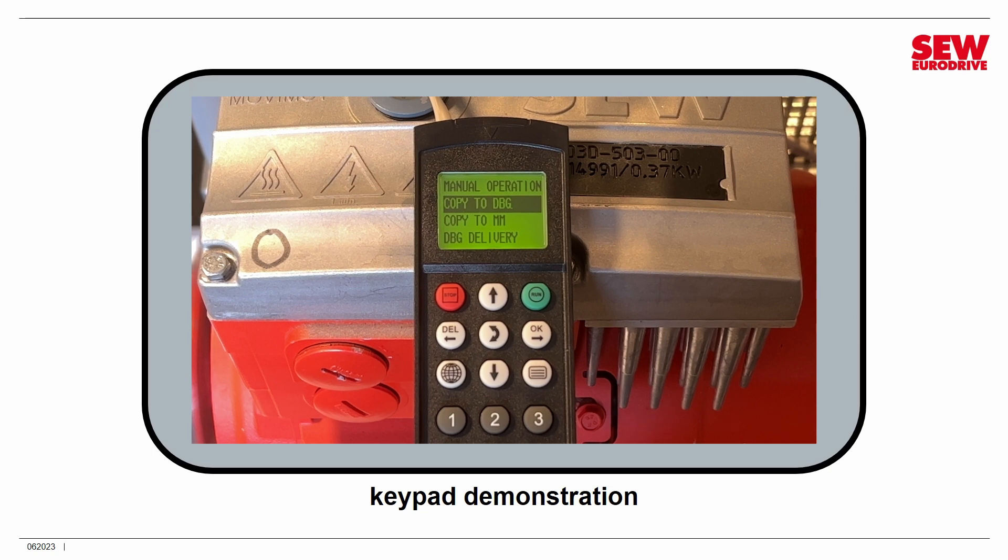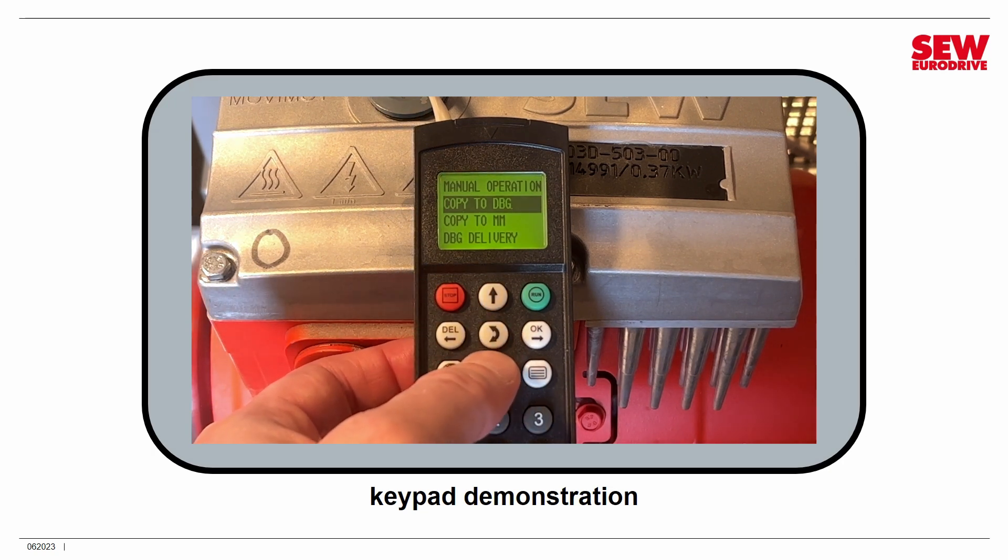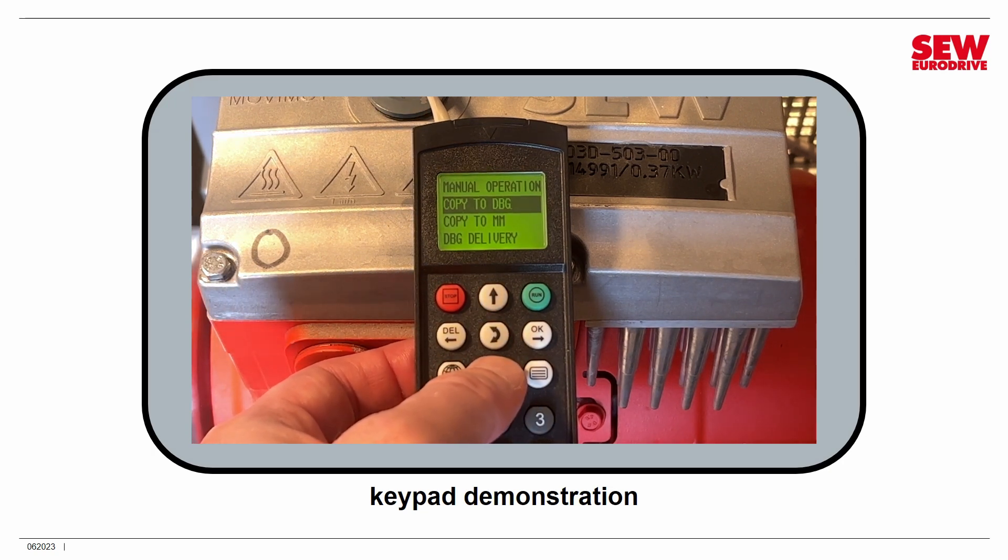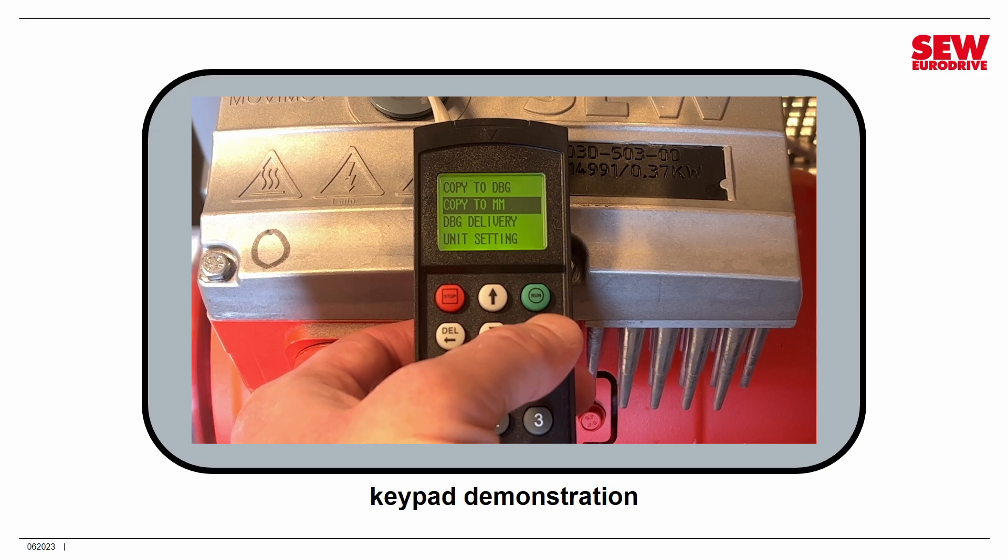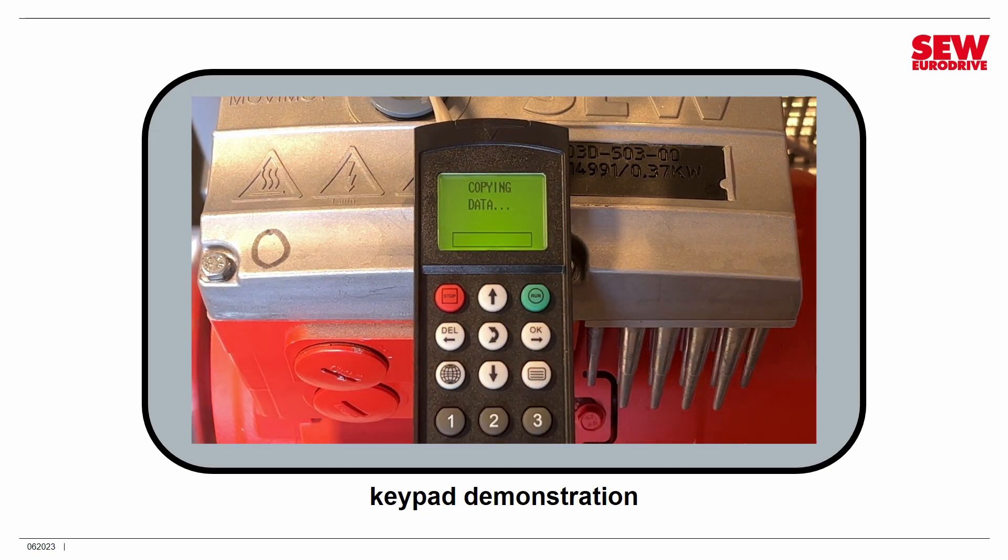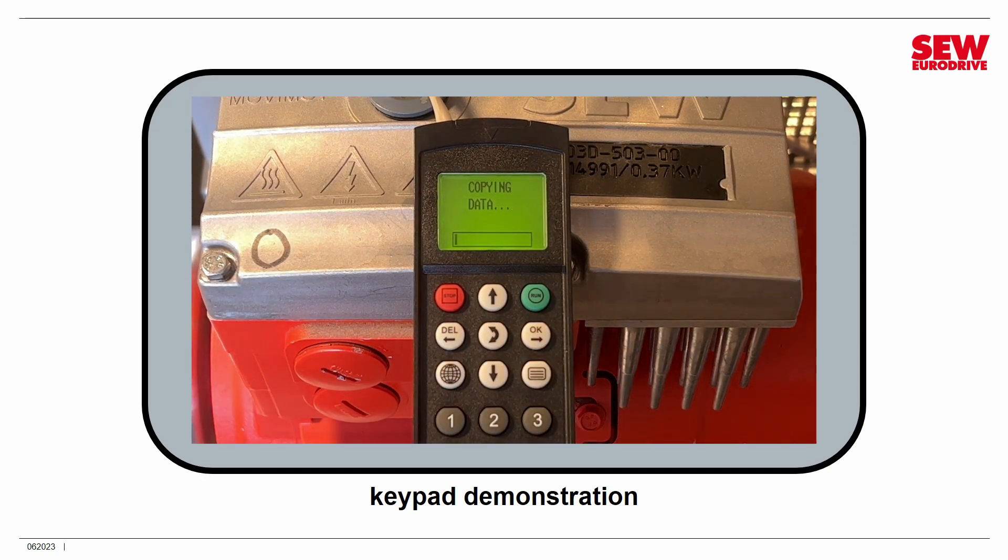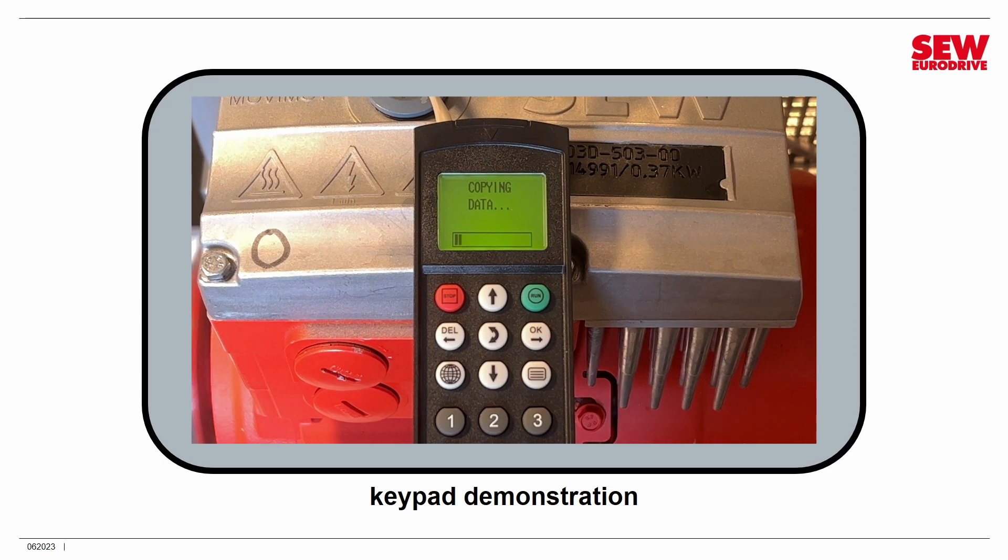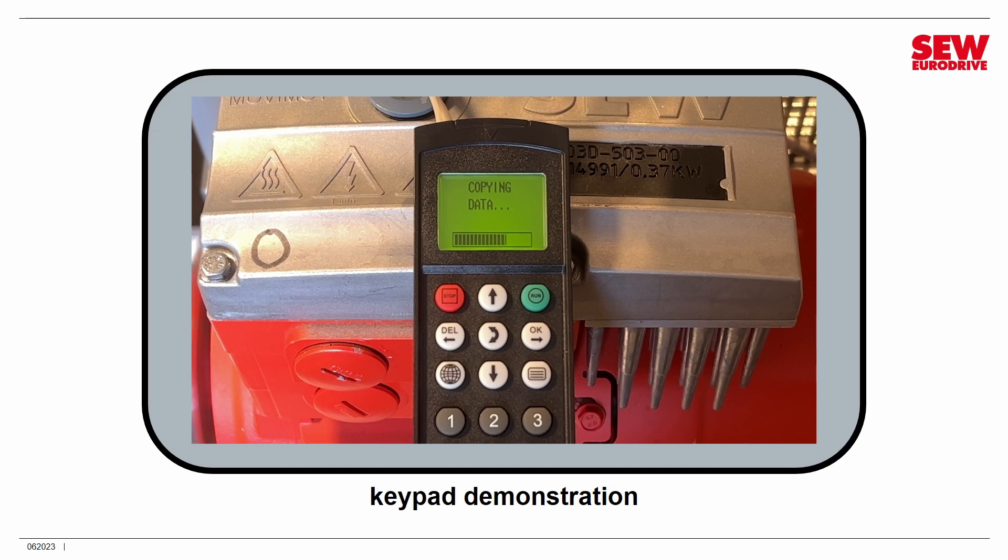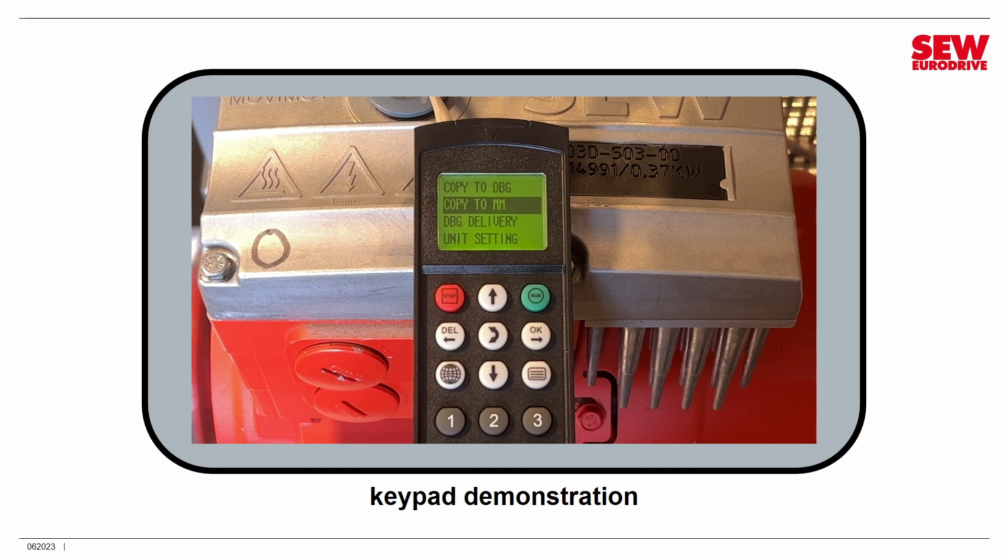Now to restore a backup into a Movimot, you just go down to the next option right below it, copy to MM, copy to Movimot, and you press OK. And again, it's just going to start the restore immediately. It's not going to give you a second chance, and it's overriding what's in the Movimot at this point. So again, be very careful before you press OK. It takes about 15 to 20 seconds to restore the parameter set. And as I said, you can use this to duplicate Movimots across multiple units if you wish to do that. And that is all I'm going to show you on the keypad, but that should enable you to do most of the things that it's really useful for.